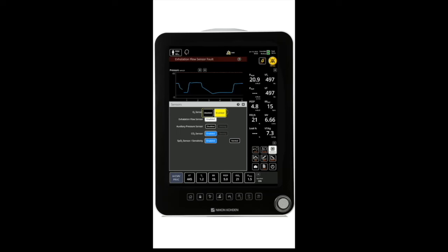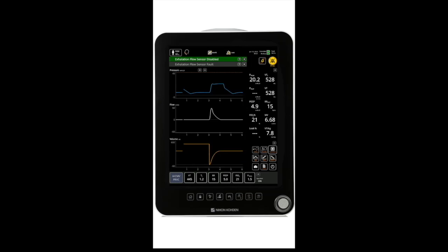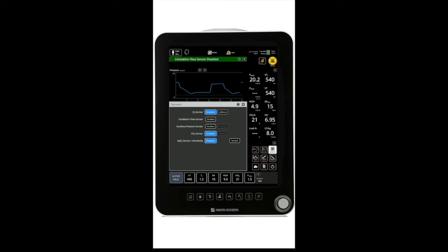Now, when it's disabled, I'm going to have no flow triggering, tube compensation, or leak compensation, and all my monitoring and alarms will be based on my inspiratory volumes. After replacing the flow sensor, I want to make sure to enable the monitoring again. So I'm going to select sensors, and I want to enable my expiratory flow monitoring again.